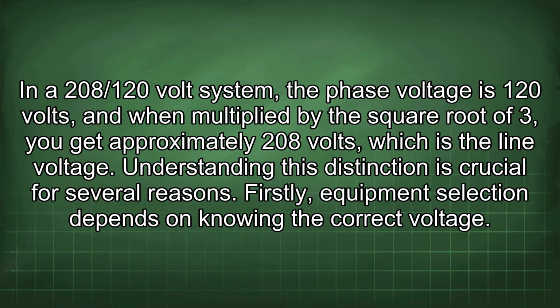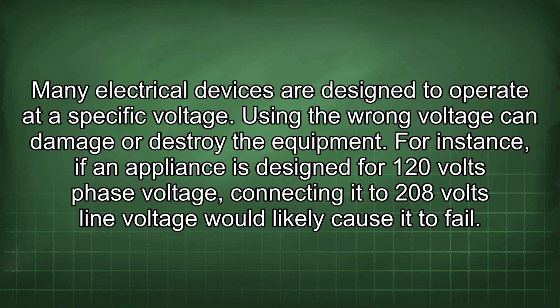Understanding this distinction is crucial for several reasons. Firstly, equipment selection depends on knowing the correct voltage. Many electrical devices are designed to operate at a specific voltage. Using the wrong voltage can damage or destroy the equipment. For instance, if an appliance is designed for 120 volts phase voltage, connecting it to 208 volts line voltage would likely cause it to fail.